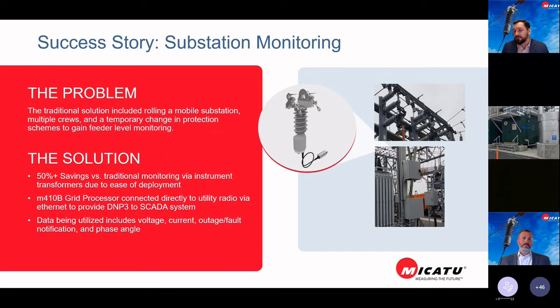Anytime you have to replace a PT or a CT or any equipment in the substation, you have to cause an outage and redirect power on the grid, which can be a very costly effort. Our solution, as pictured with our line hanging sensor, the RG235, can be hung with a hot stick or a glove by a single person in a bucket truck. There's no need for bringing in a mobile substation, causing outages, or having large crews and lots of equipment.